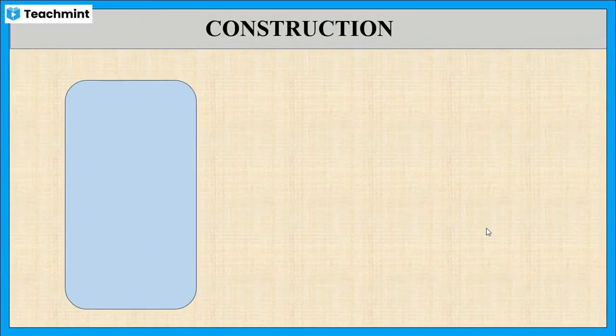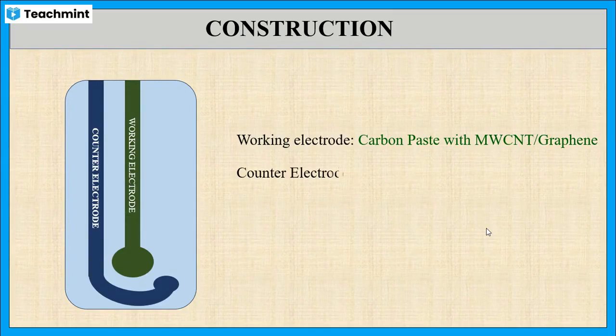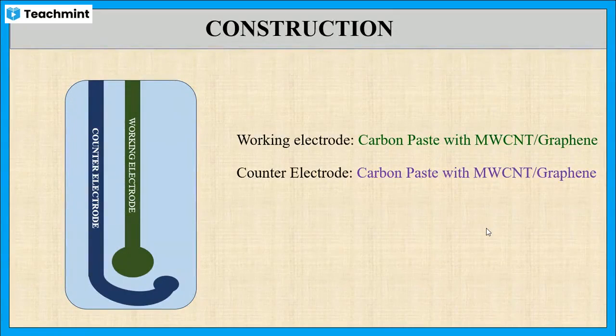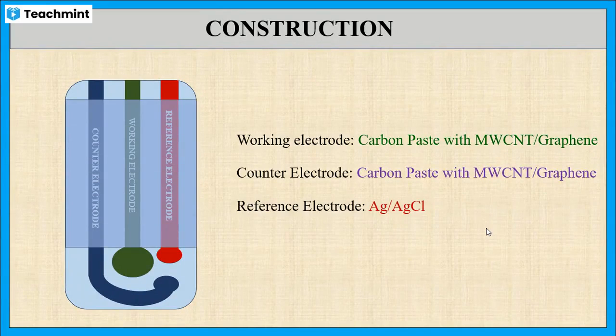It contains a plastic strip on which three electrodes are printed using screen printing technology. The working electrode and the counter electrode are printed with carbon paste along with multi-walled carbon nanotubes or graphene. The reference electrode is printed with the ink of silver-silver chloride. The upper part of the sensor is sealed with insulating material, and the strip is connected to an electrical connector and immersed in the analyte solution for measurement.